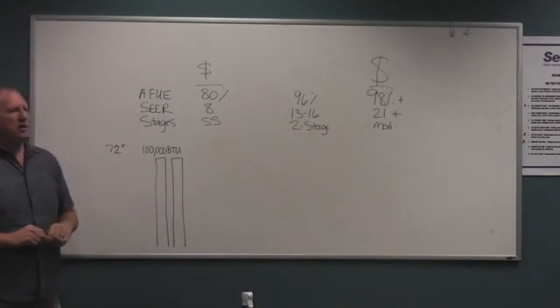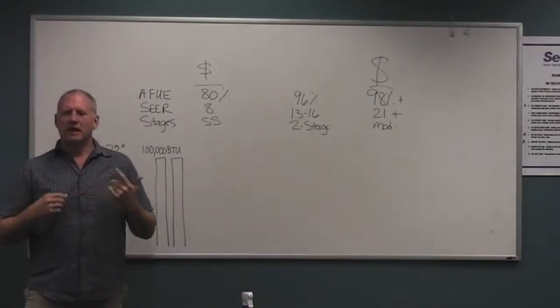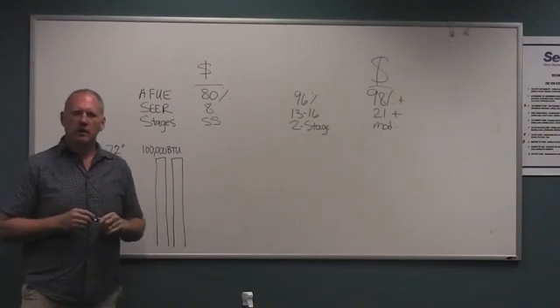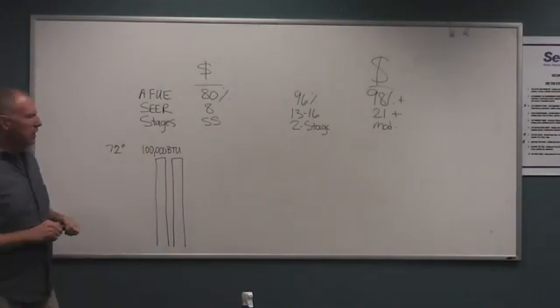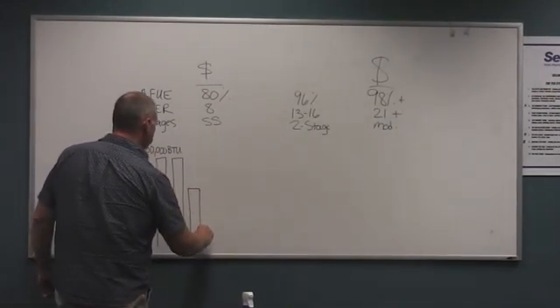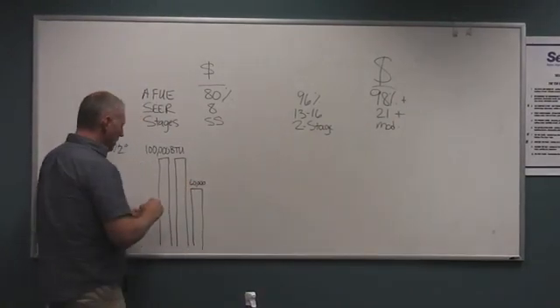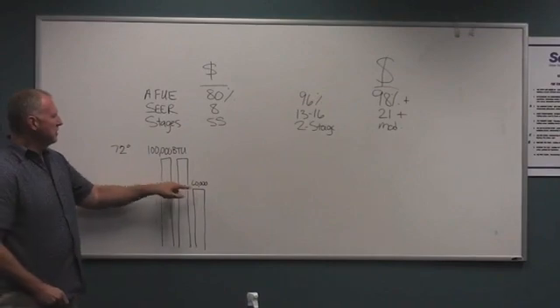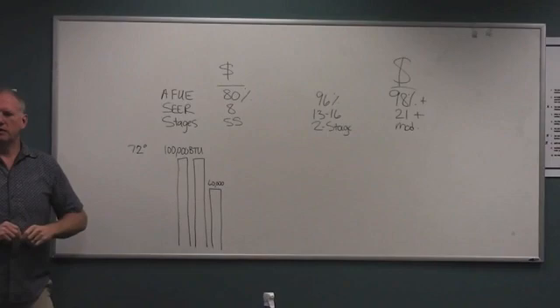First of all, what we've done is we've gone through a load calculation and figured out exactly what the needs are for your home. You don't need a 100,000 BTU furnace. This is actually way oversized for your home. What you need is actually a 60,000 BTU furnace. Right off the bat, we're going to save you a whole bunch of money because every single time your furnace kicks on, instead of kicking on to 100,000 BTU, it's going to kick on to 60,000 BTU.